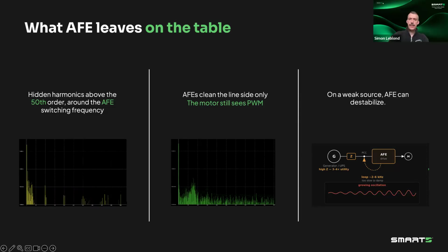And finally, I mentioned generators as a weak source. It could also be a UPS. The active front end is actively monitoring the grid, and it has a control loop to compensate for those harmonics. When you have that weak source, the control loop can be too slow to damp the interaction with the generator, and you can create an oscillation. It's a potential reliability issue that you don't necessarily think of because you're designing for the grid. But with uptime front and center, that generator should be addressed from the start. So you do have a cleaner grid, but there are things that are left open.